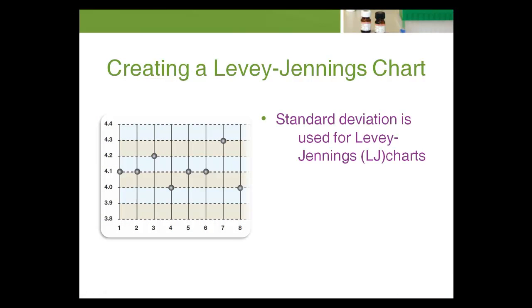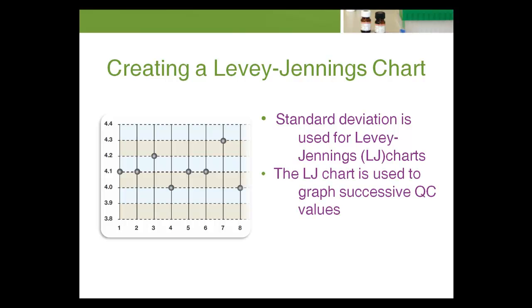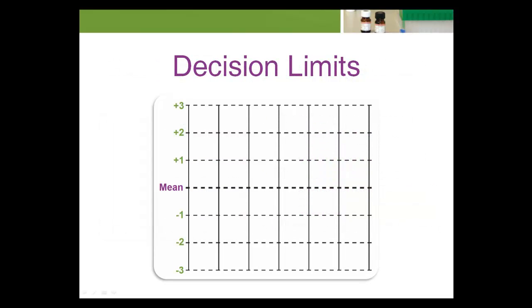Welcome to Chapter 3: Levy-Jennings Charts and Westgard Rules. Standard deviation is commonly used for preparing Levy-Jennings charts. The Levy-Jennings chart is used to graph successive run-to-run or day-to-day quality control values. A chart is created for each test and level of control. The first step is to calculate decision limits. These limits are positive-negative 1sd, positive-negative 2sd, and positive-negative 3sd from the mean.